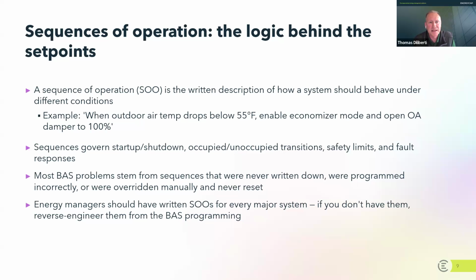Another term that's used a lot is this idea of what's called a sequence of operation. So just reading this, because it's important to understand this very clearly, a sequence of operation is the written description for how a system should behave under different conditions. And although it's an electronic system, a digital system, the user has to decide how that system is going to adjust or change. So having these sequences of operation documented and in a location that you as the user can understand is really critical. And if you draw your attention to the bottom couple bullets here, most building automation system problems stem from these sequences that never get written down. They never get programmed correctly.